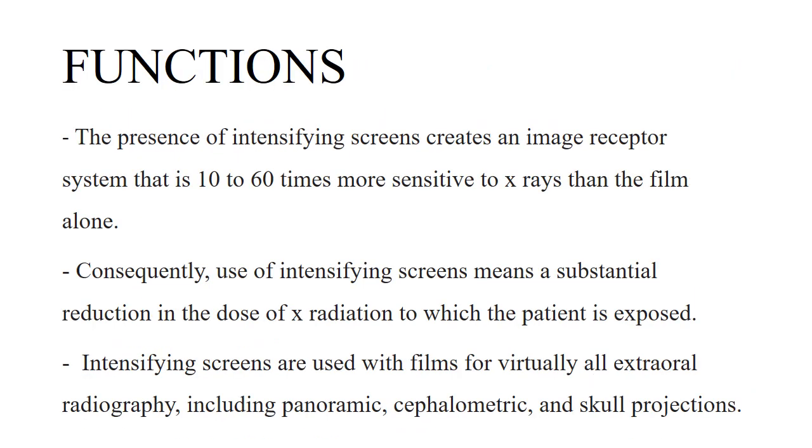Functions. The presence of intensifying screens creates an image receptor system that is 10 to 60 times more sensitive to X-rays than the film alone. Consequently, use of intensifying screens means a substantial reduction in the dose of X-radiation to which the patient is exposed. Intensifying screens are used with films for virtually all extraoral radiography, including panoramic, cephalometric, and skull projections.